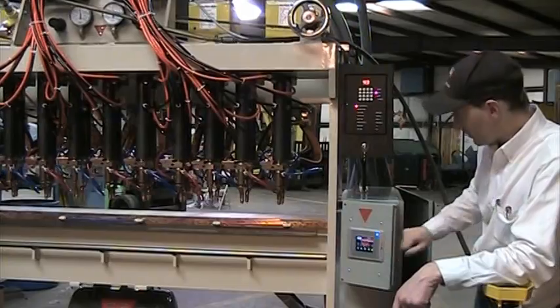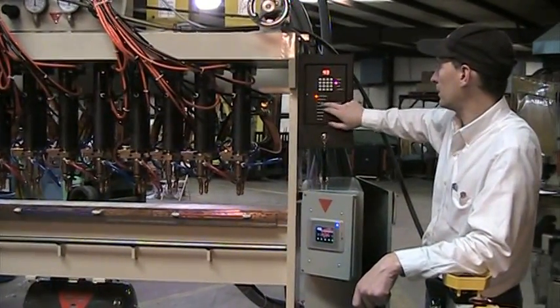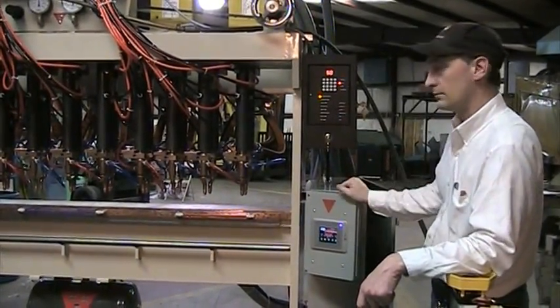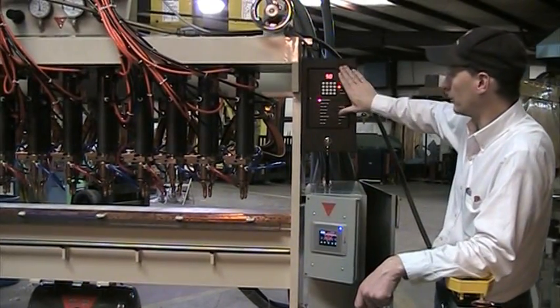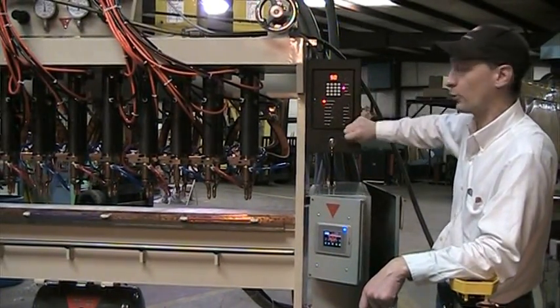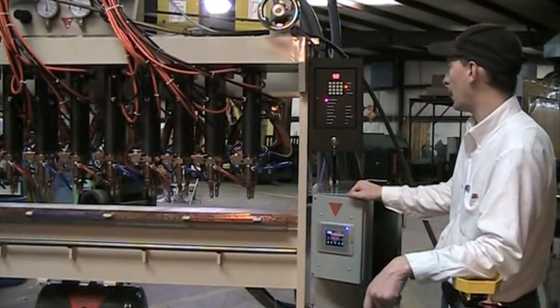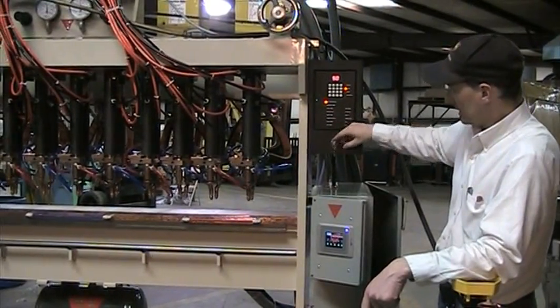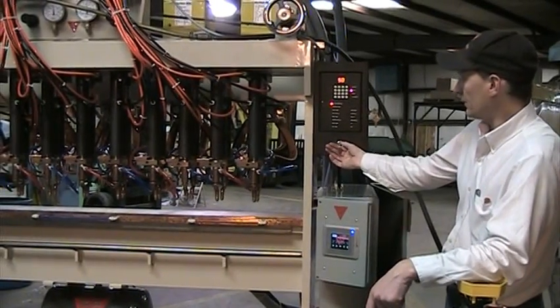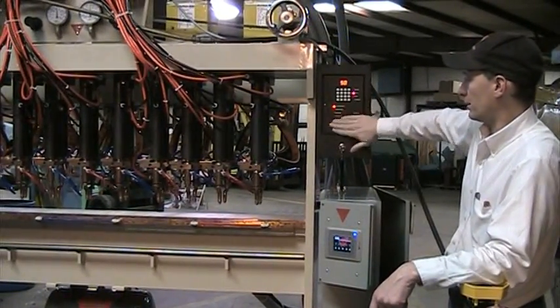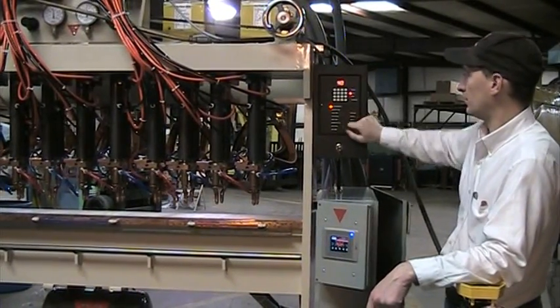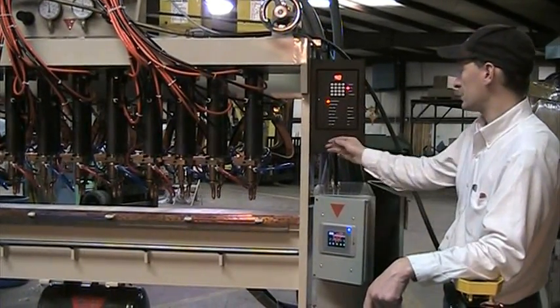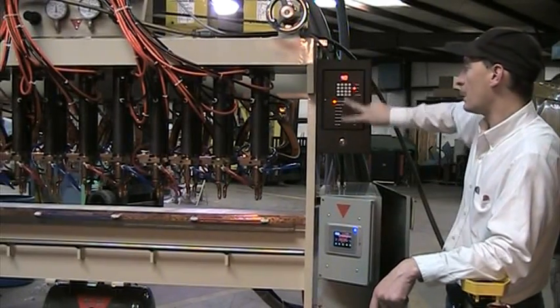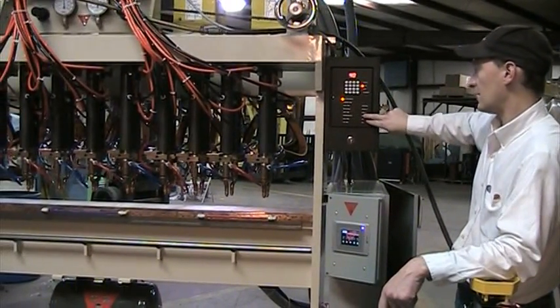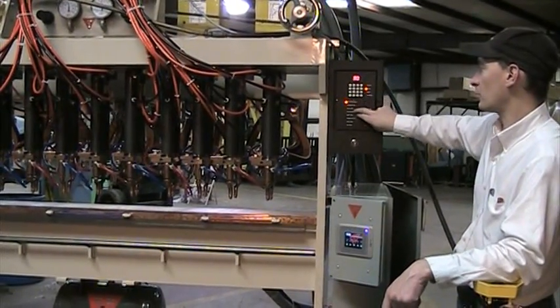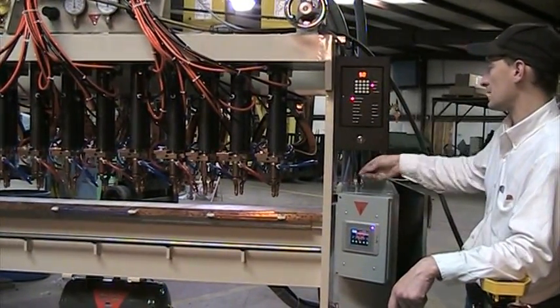As we select the number of transformers, we've set it up to also have the corresponding number on the control. So 5 transformers start on 50, 4 transformers 40, 3 30, right on down the line. Finally, on this side you've got your program lock. If you lock this, it disables the B button so you can no longer get into the program, but you're still able to change to the different program numbers. So with this locked and the key pulled, the operators will be unable to alter the program that is in the control, but they will be able to change between the corresponding transformer numbers as necessary.